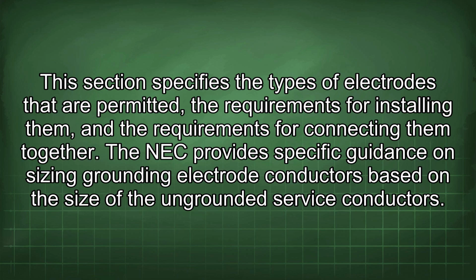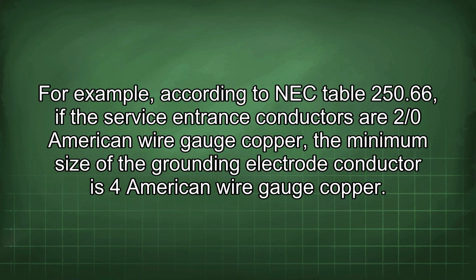This section specifies the types of electrodes that are permitted, the requirements for installing them, and the requirements for connecting them together. The NEC provides specific guidance on sizing grounding electrode conductors based on the size of the ungrounded service conductors. For example, according to NEC Table 250.66, if the service entrance conductors are 2/0 American wire gauge copper, the minimum size of the grounding electrode conductor is 4 American wire gauge copper.